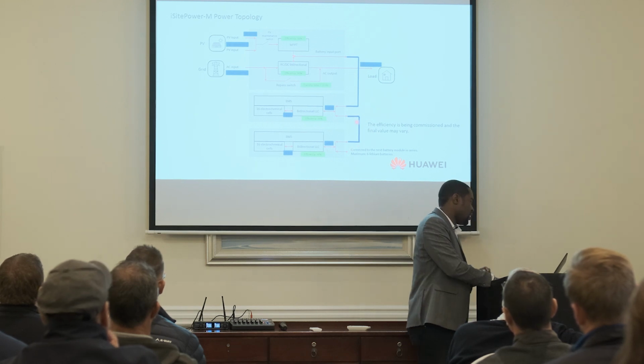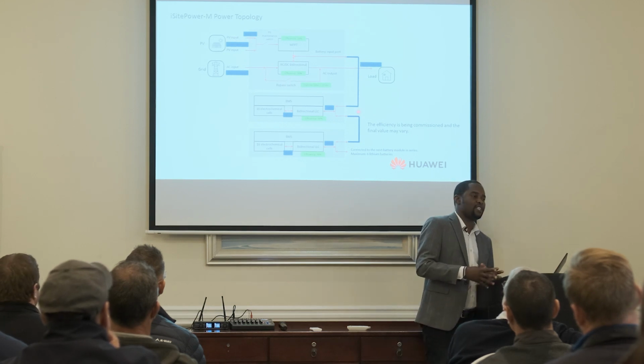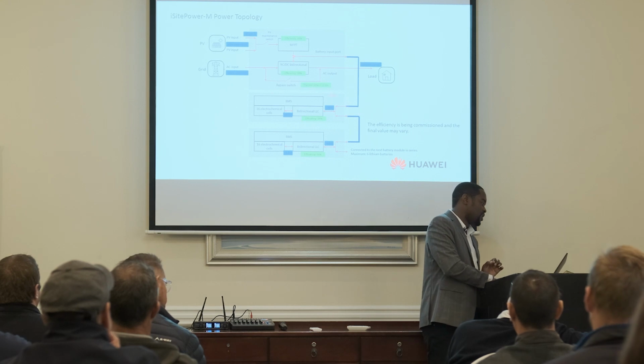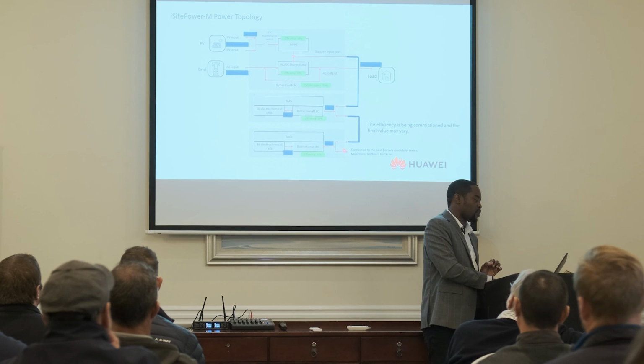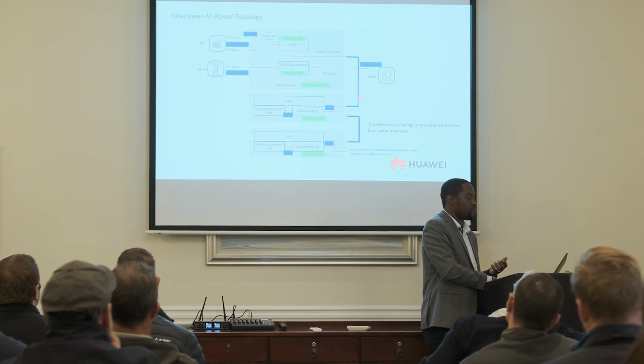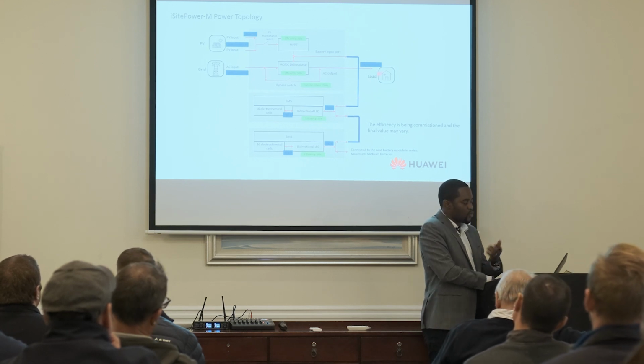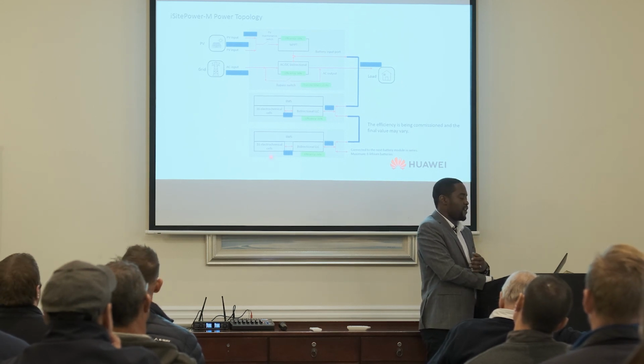So your batteries here are actually giving a 400 volts output going to this bus bar, and your strings from this side are also coming to the same bus bar. So the advantage of these high voltage systems is when the PV is coming into the same bus bar, it finds that the bus bar is already at 400, which means the bus bar is already afloat. So it's easier for the PV to convert 400 volts DC to 230 AC voltage, rather than coming to the bus bar where it finds a low voltage battery, which is at 51.2 volts.